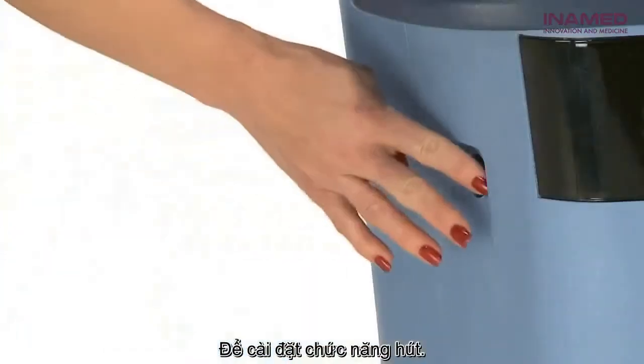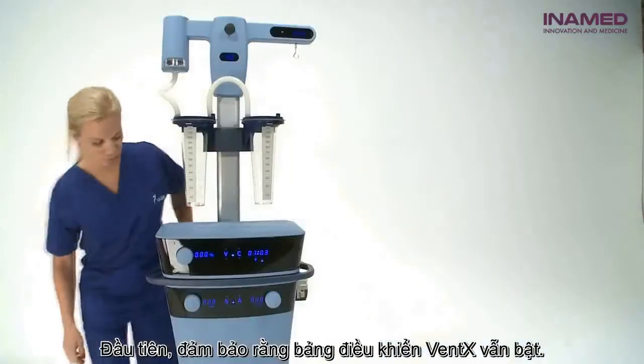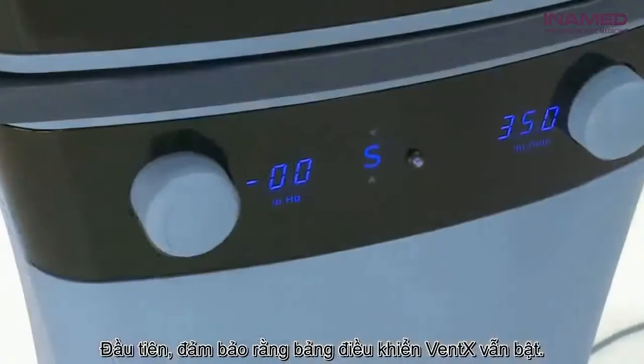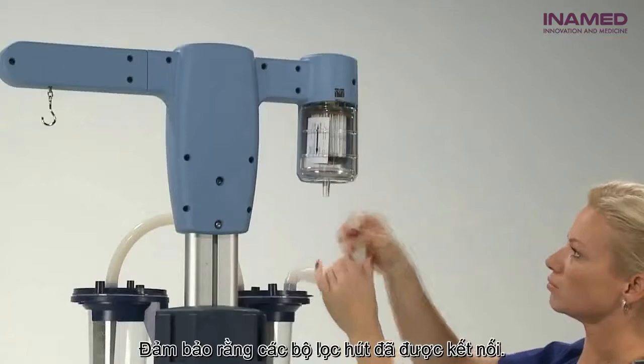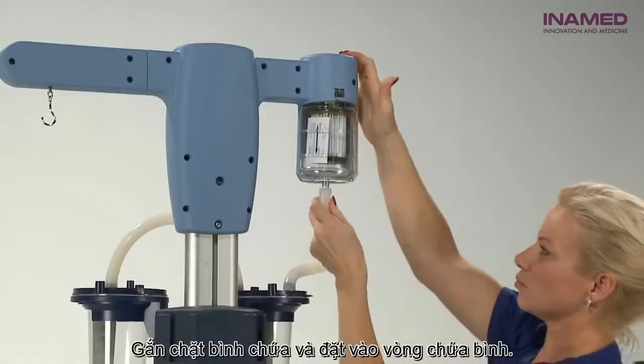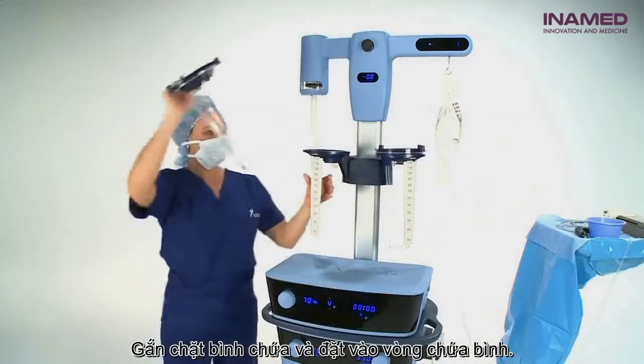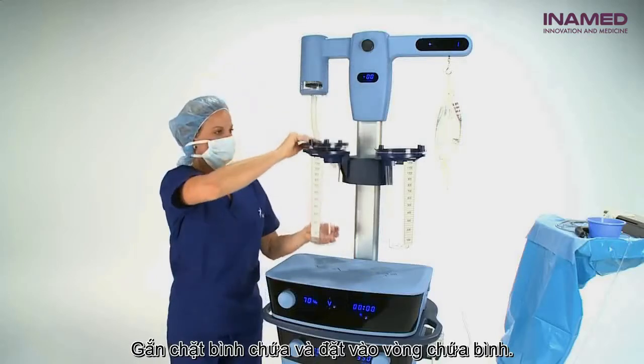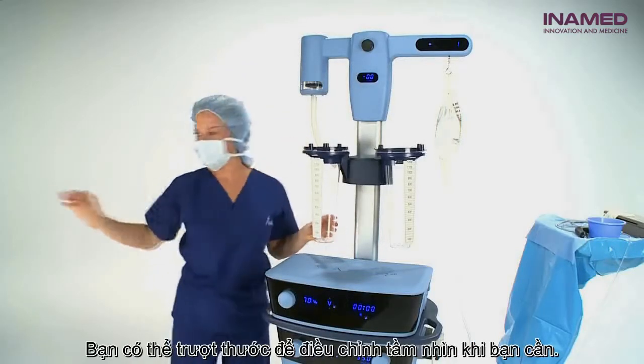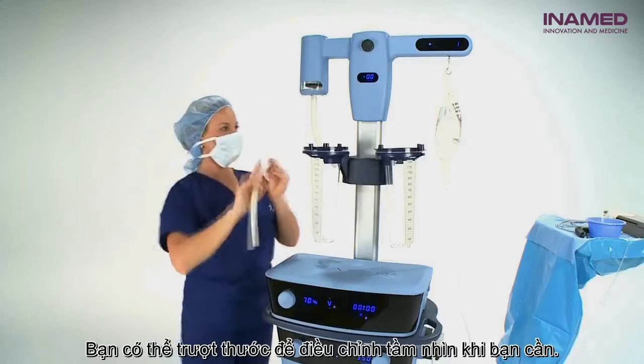To set up for aspiration, first, ensure that the VentX console is still on. Ensure that the suction filter is connected properly. Tightly attach the canister lids to the canisters and place in the canister rings. You can slide the ruler to adjust for your viewing needs.